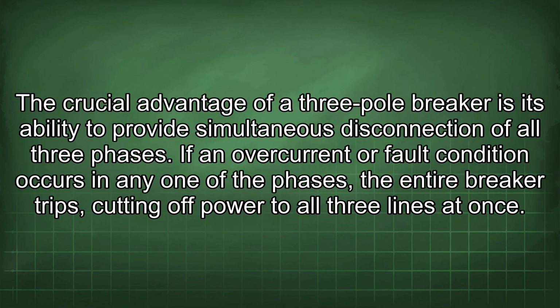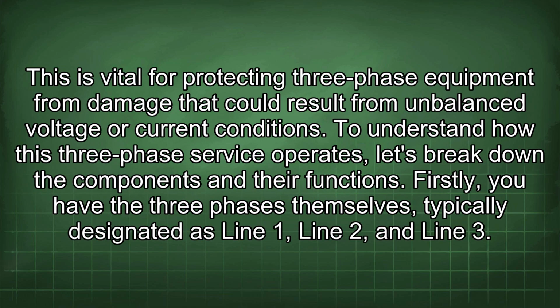The crucial advantage of a 3-pole breaker is its ability to provide simultaneous disconnection of all 3 phases. If an overcurrent or fault condition occurs in any one of the phases, the entire breaker trips, cutting off power to all 3 lines at once. This is vital for protecting 3-phase equipment from damage that could result from unbalanced voltage or current conditions.